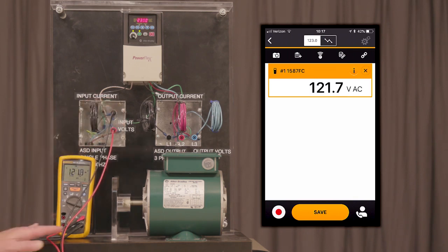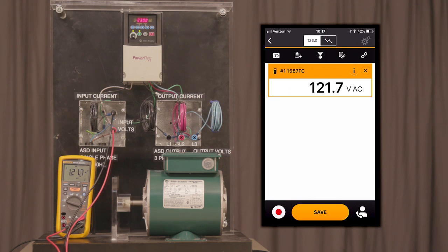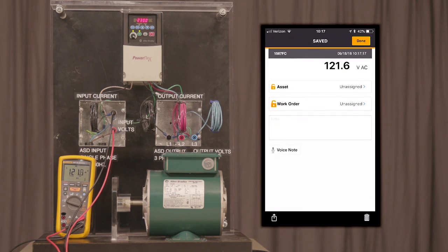So let's do some voltage measurements on the input voltage for the drive. I'm going to turn my meter over to volts and confirm it's there. Let's make sure the test leads are put in the correct position, and we can make our input voltage connection. As you can see, the input voltage going into our VFD is 121 volts.